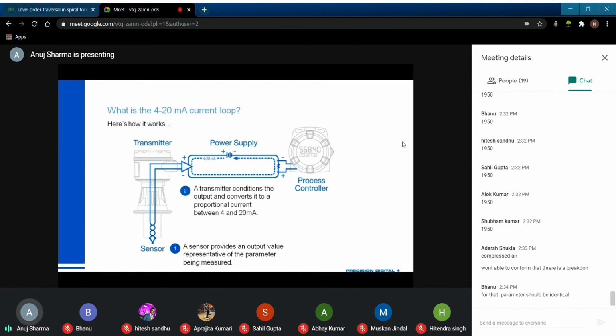You've got a transmitter. The transmitter is what's responsible for actually creating that 4 to 20 milliamp signal and regulating it. And then you've got some kind of receiver or multiple receivers. In the graphic here, we've got it being a process controller, but it could be any number of devices. The last element is the power supply, which may or may not be an entirely separate device. And I'm going to go a little bit more into detail on each of these now so that you can have a better understanding of how these all interact.